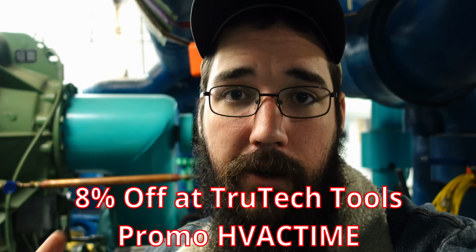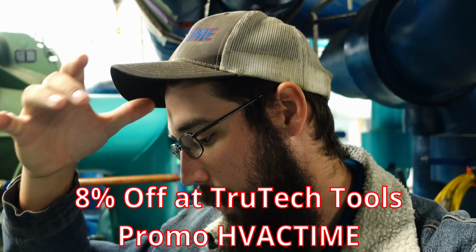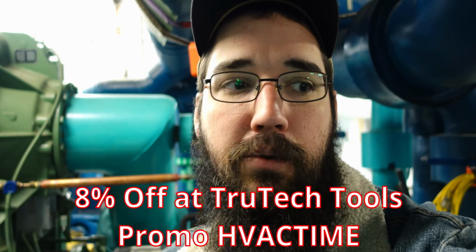Once we got done chasing leaks, we pressurized up to just shy of 90 pounds, held it overnight, and it did perfect, so we decided to move forward. We've got time frames to stick to. We're going to pull the vacuum, get it pulled down, and do a standing vacuum test as well to make sure it holds. Then we've got 1,500 pounds to pump into the system. Keep in mind, 200 of that is what we actually recovered; the other 1,300 we're going to go pick up today at the job site. That order came in yesterday.